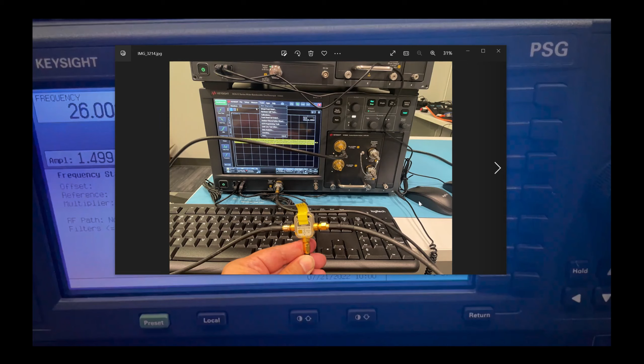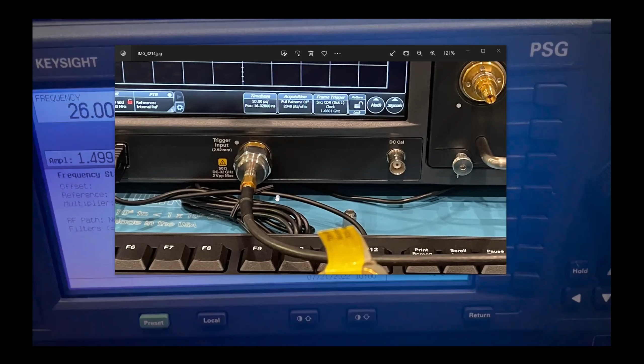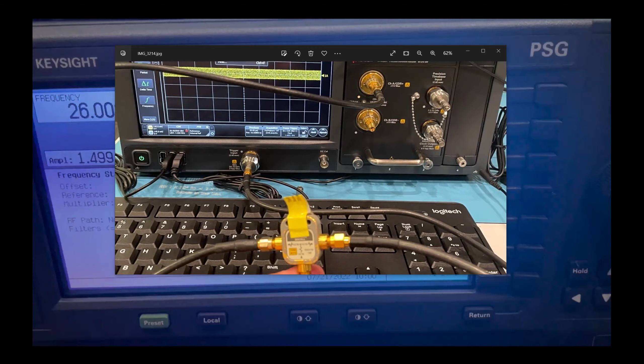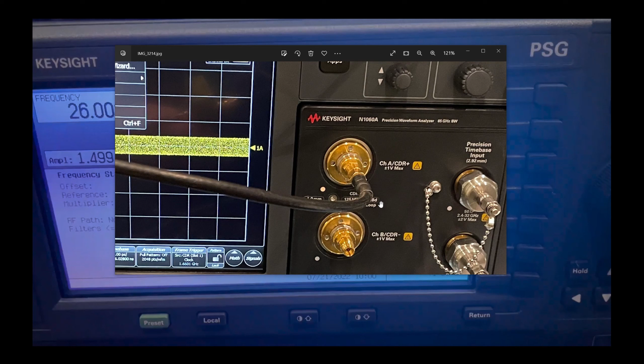Once you split this out, you would take that and connect one to the trigger input on the front of the DCA itself, so that one needs to be triggering that, and the other end needs to be going into the N1060 precision waveform analyzer, either channel A or channel B. You can select that in the GUI. I suggest having couplers on the ends that are 2.4 millimeter if you can. Otherwise, you're going to have to change those out, and that just makes an extra step that's unnecessary.